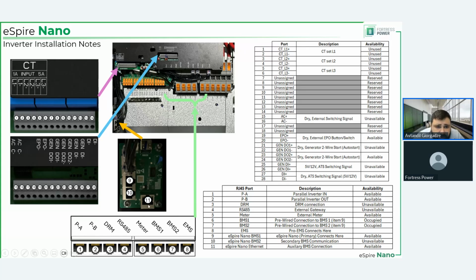This yellow arrow shows the communication board that is already there, and it has 2 ports, BMS1 and BMS2. BMS2 port is not to be used. BMS1, number 10, will be used to communicate from the inverter to the primary battery. So if you have one battery, that's your primary battery. If you have multiple batteries, the primary battery is the first one in the chain, the one that communicates to the inverter. Number 11 is for hardwire internet connection, right?